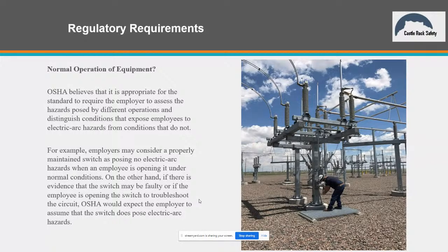Basically, when 1910.269 started to develop this revision, at the time, if you guys remember, and James, I know you remember this, the 70E standard allowed anyone working under the exposure of 2 calories to wear cotton clothing. It's been a little while, but they took that out and went to 1.2 calories. So when OSHA was writing their standard, that was the way 70E was still written, so they adopted that. By the time the standard got out, NFPA 70E had changed it, and OSHA just said, screw it, we're staying with the 2 calories.